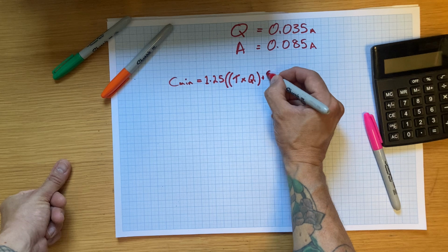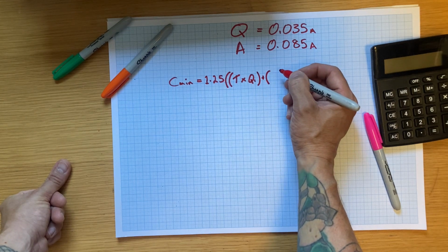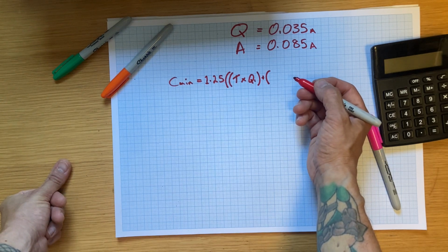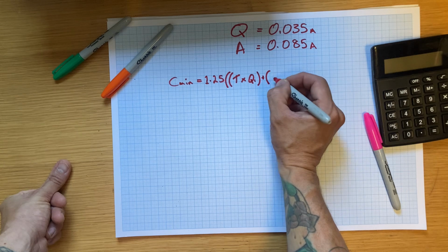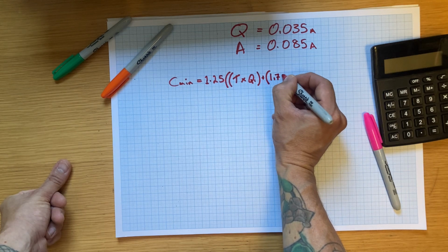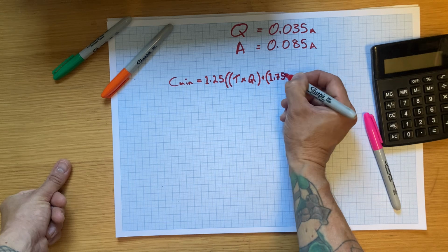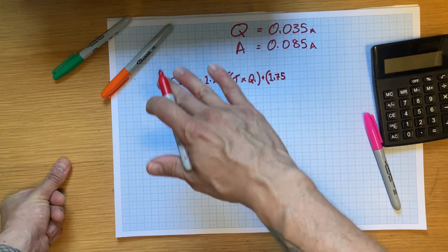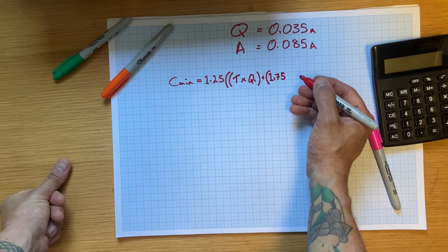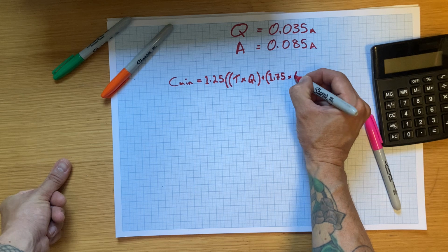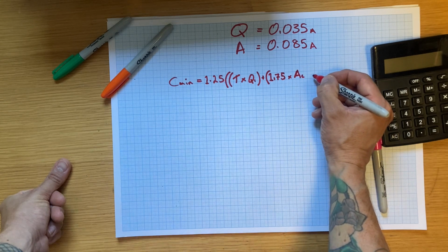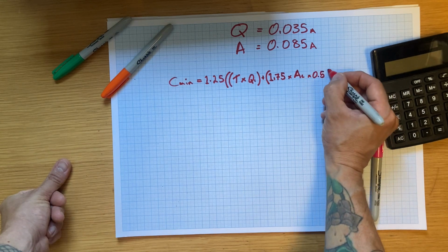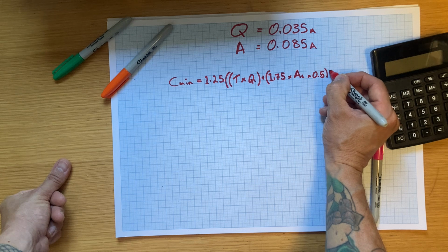Then that is plus our derating factor, right? So age of batteries, that kind of thing. They wear out, they last about 5 years. So we tend to use 1.75. Because it's a derating factor for batteries, we want them to go bigger, whereas for derating for cable calcs, you kind of go the other way, you end up carrying less. That times our alarm load, and that is then times 0.5.